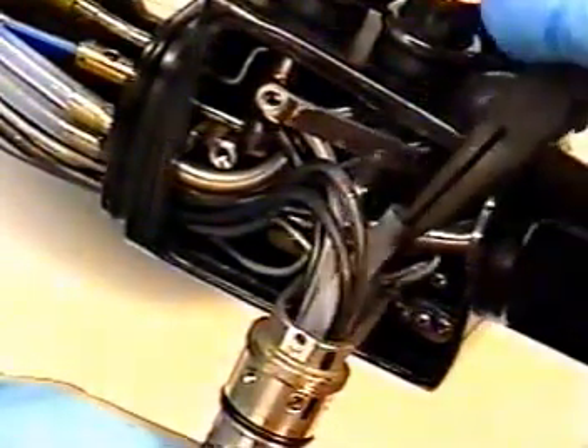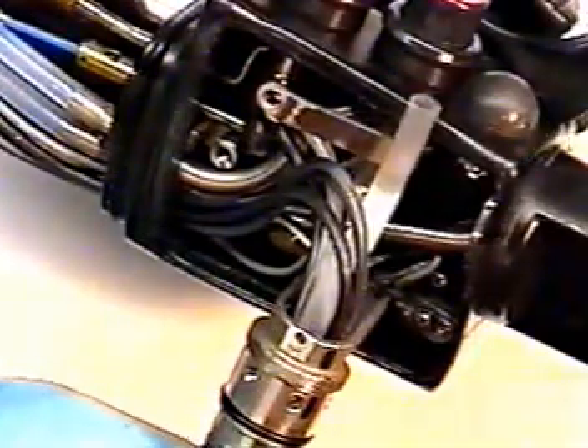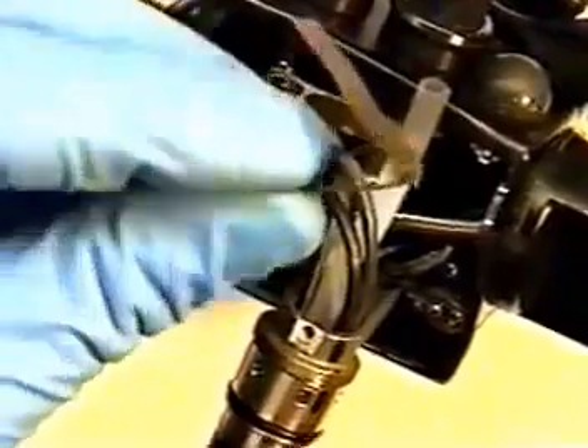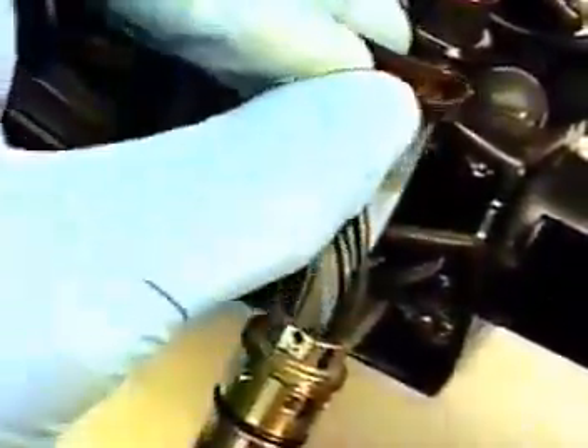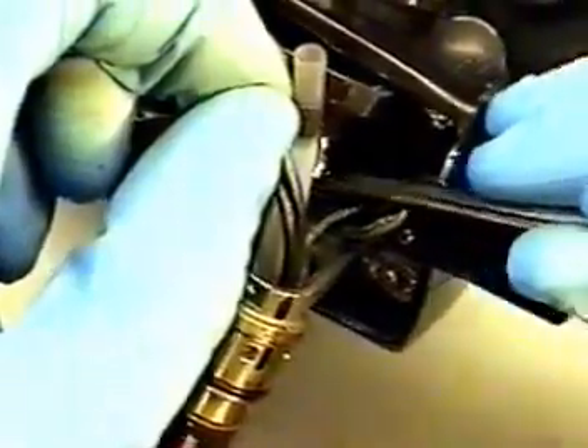Using a pair of pliers, pull out the suction channel, and using a piece of emery cloth, grab your suction channel and take a pair of tweezers and gently pry the tweezers in the opening of the suction channel. This will let us slide the suction channel up onto our suction pipe. Do not force the tweezers in too far, because that will make too large of a gap to fit over our pipe.